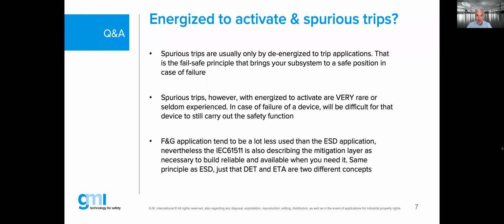So, first bullet, spurious trips are rare, we mentioned that. They are often seen in de-energized, but not often in energized to activate. However, a spurious trip would mean that the output would go to an energized position. It would be able to energize, and in case of a failure of that device, it would be very difficult. Assume that you have to energize a solenoid. You have to open a solenoid, but the solenoid is stuck. Well, that type of problem is the same sensitive problem for de-energized versus energized.